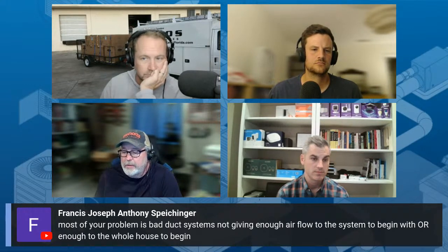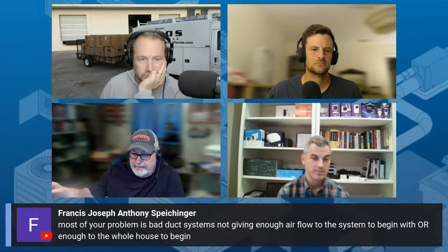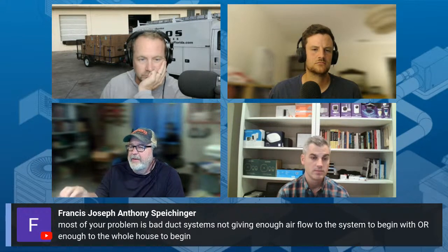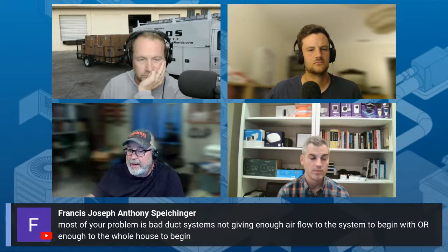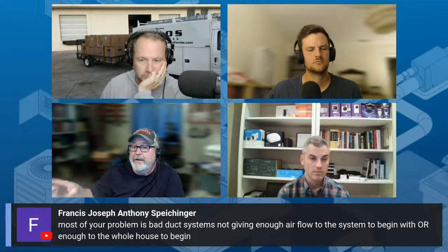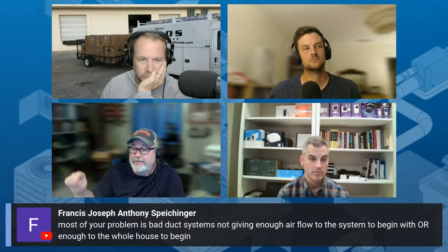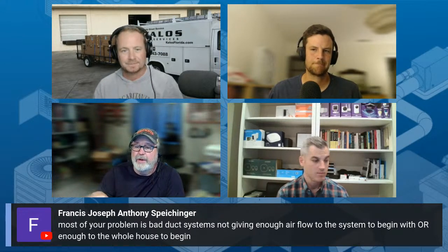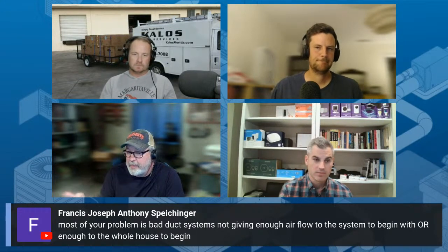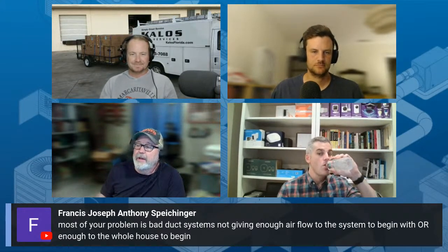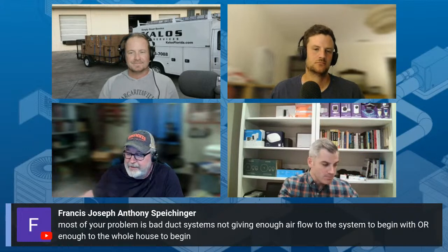Sure. You can look right in the expanded data tables. Not so much on the heating side, it's kind of weird, but definitely on the cooling side, capacity drops when airflow drops across the coil. You can see it right in the tables. And another interesting thing is SEER gets worse too. So when you reduce airflow, it's a double whammy. You lose capacity and you lose efficiency. And so that's one reason to have good airflow.